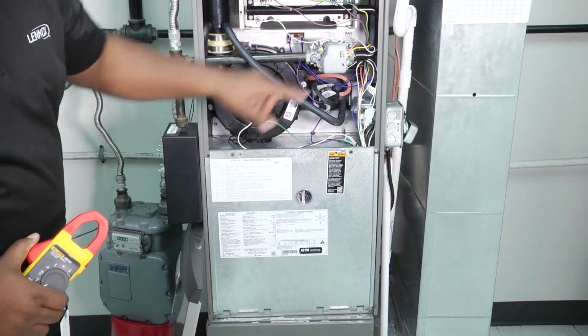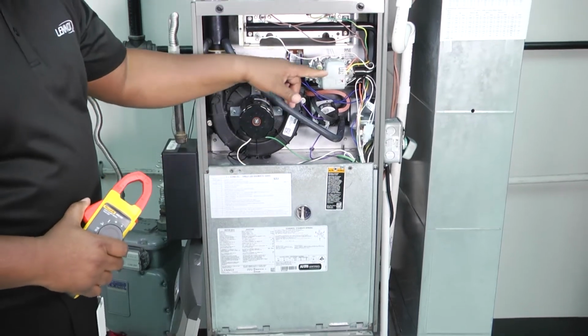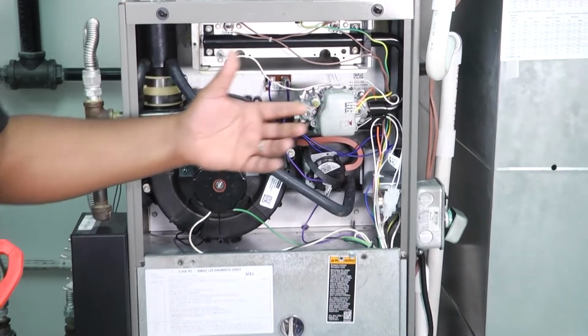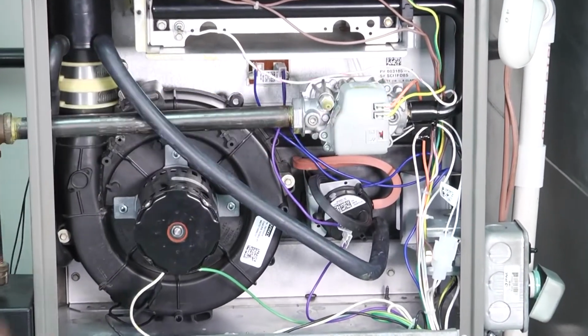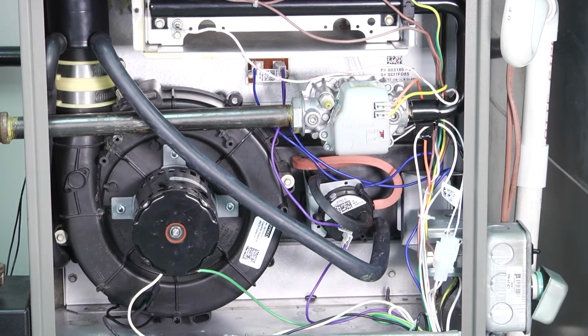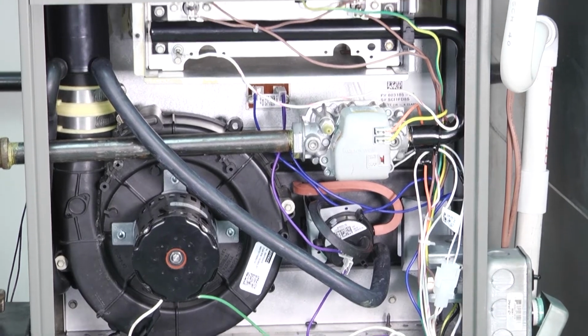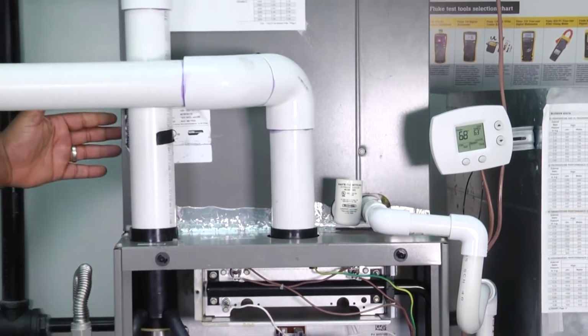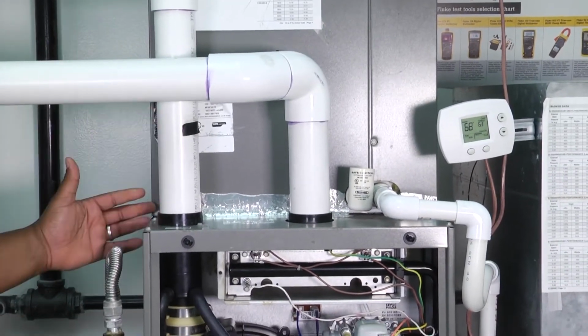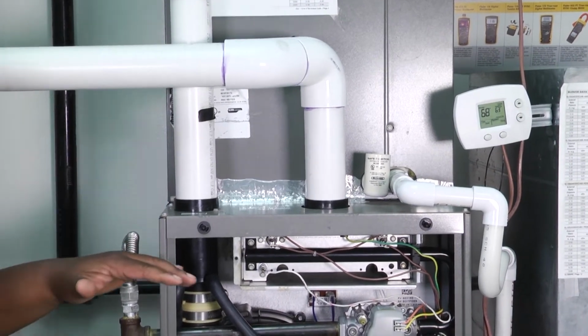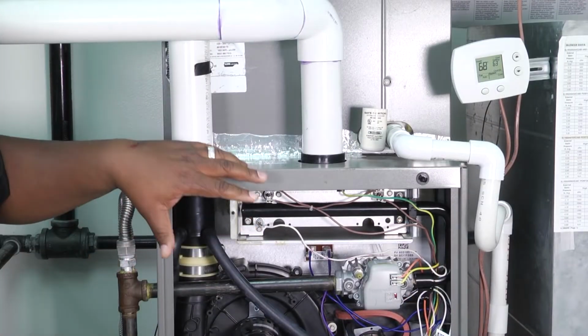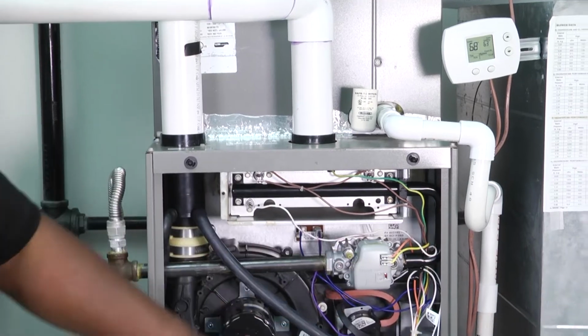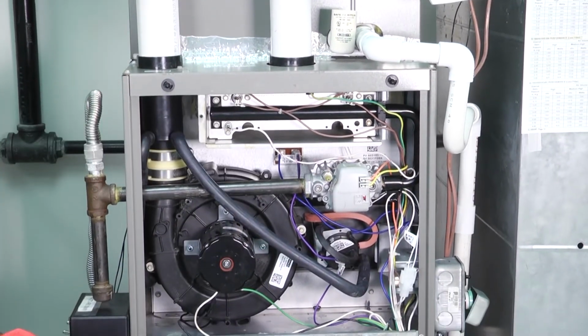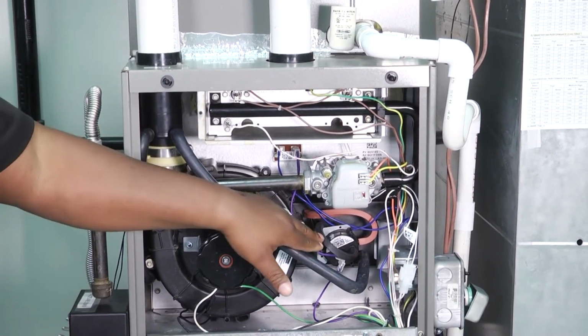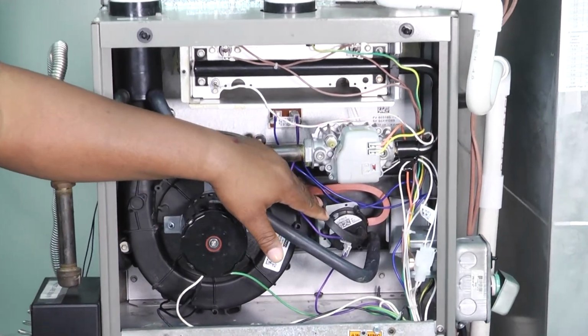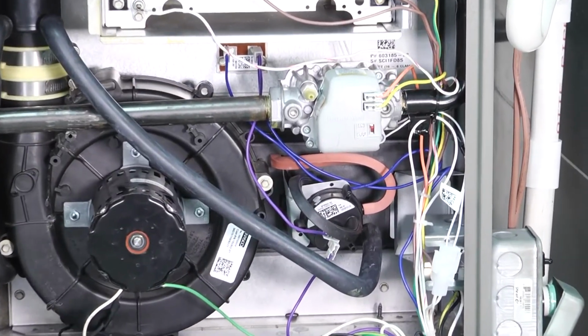The other thing you want to check is your input and output gas pressure. You'll use your manometer to check gas pressure and make sure it's okay. We may even use our manometer to check static pressure throughout the system, as well as making sure all our wire connections are good, all our safeties are working properly, especially the pressure switch, and that hoses and tubes are clean, and so on.